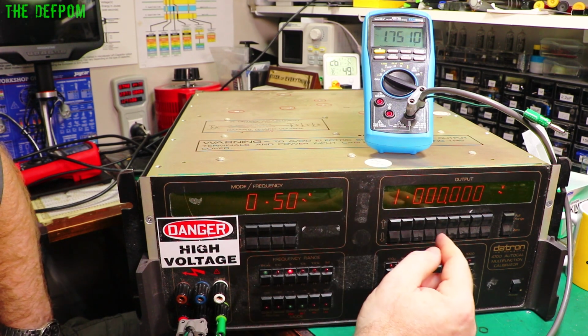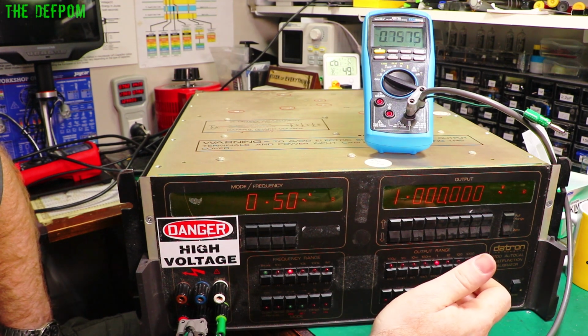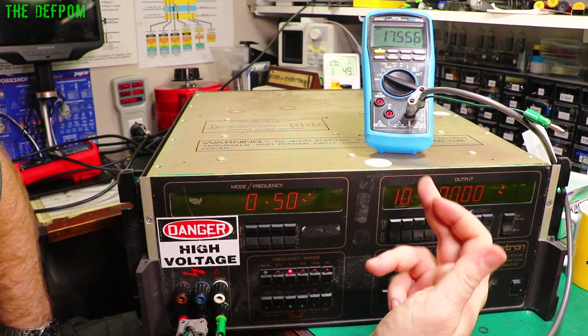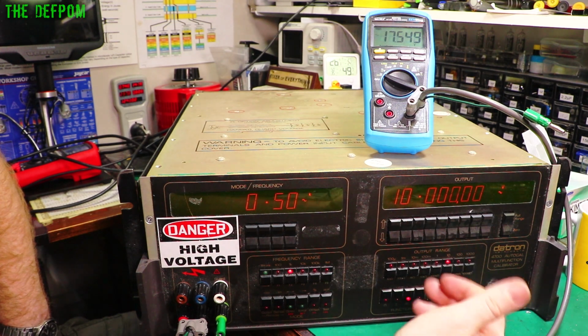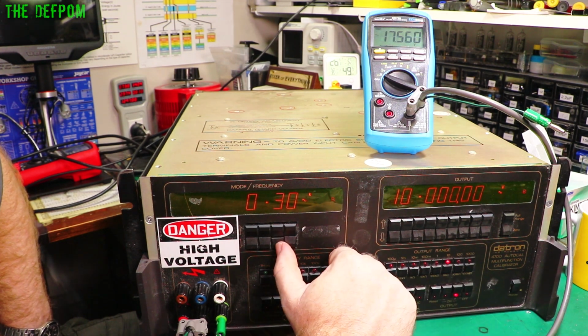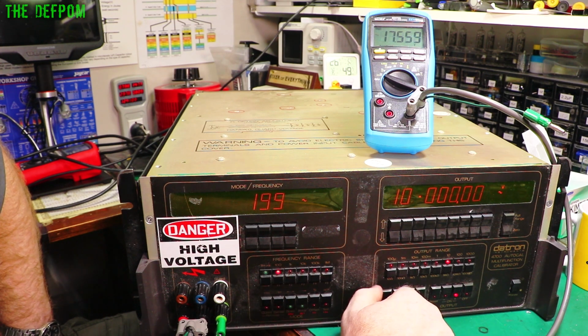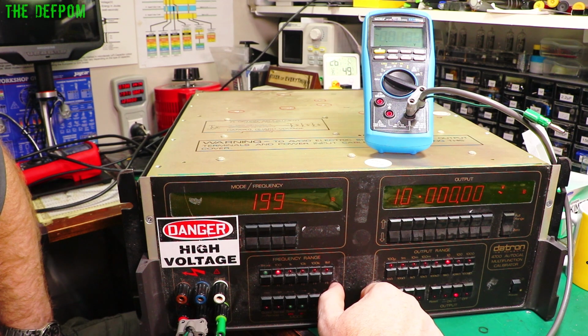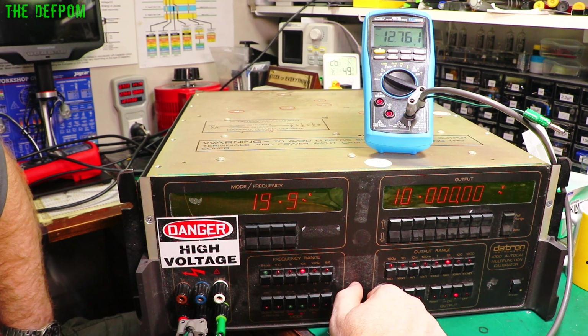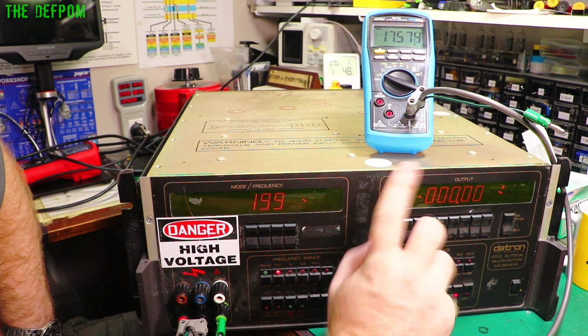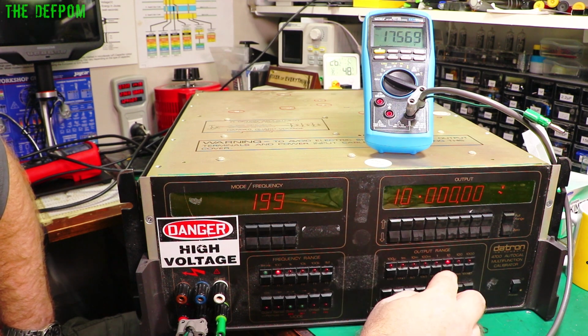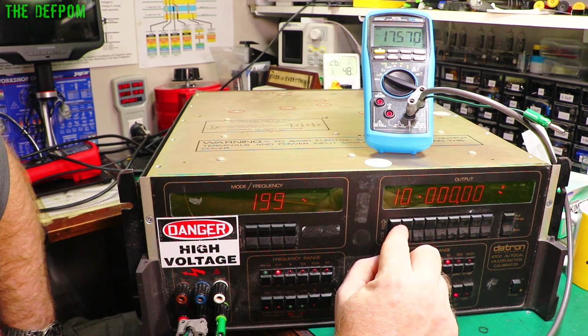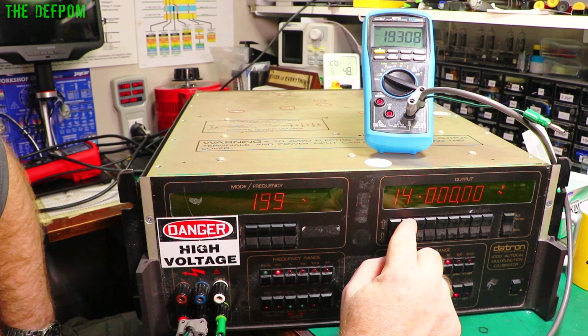1 volt, I'm getting 1.75. 10 volts, getting 17. Same ratio error. If I change this frequency, does that change it much? No. Let's just change ranges. That beep's kind of disconcerting. 10 kilohertz. 1 kilohertz again. Yeah, so the frequency isn't related really to the voltage offset here. So let's go up a bit more if I can. Probably only going up to 19 on this range.